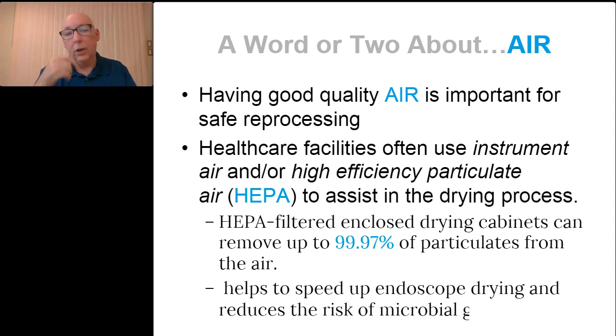All air cleaners, though, require periodic cleaning and filter changes. So again, just like with the pre-filters, that is the first line of defense, the HEPA filter also needs to have regular maintenance. Typically, if you check your drying cabinet manufacturer's IFU for the frequency of changing that HEPA filter, it's annually, once a year. The pre-filter can be changed most of the time by end users. They're usually pretty accessible for end users. The HEPA filter more than likely is going to require maintenance facility folks to come down to your department and replace that filter.